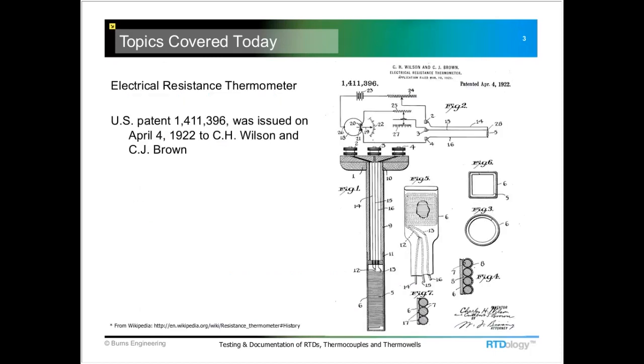And first off, we'll start out with just a little bit of history of the RTD. It was first patented back in 1922, and it really hasn't changed a whole lot since then. In its most basic form, it's platinum wire wrapped around a mandrel and has a 3 or a 4 wire circuit connected to it to eliminate the lead wire resistance.